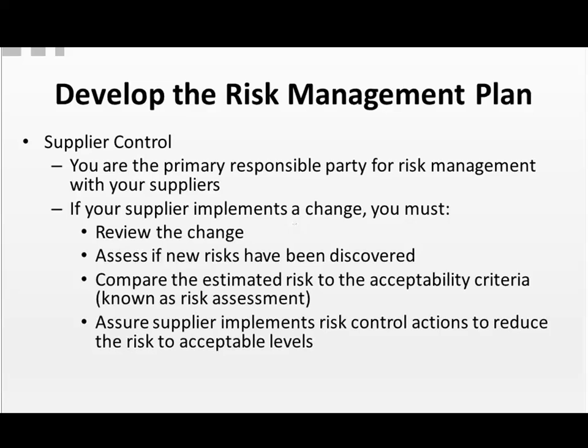Apparently, that small change that they thought was essentially innocuous turned out to really impact dosage levels that were provided to patients, which would have resulted in a whole host of issues, not to mention some recalls of the device. So supplier controls are quite important. They are an extension of your organization.